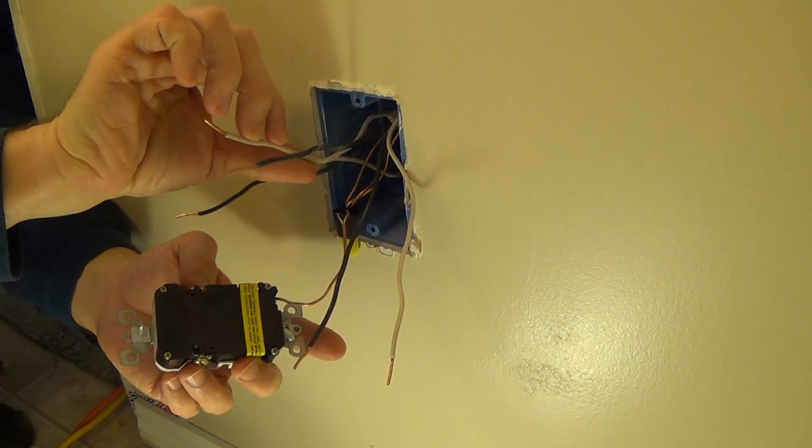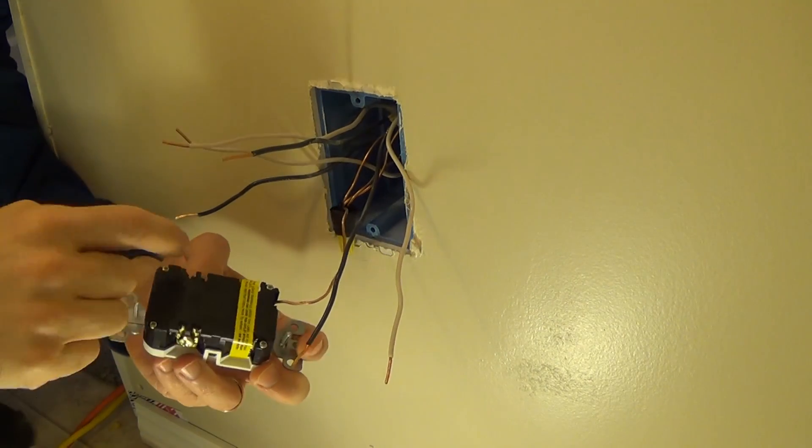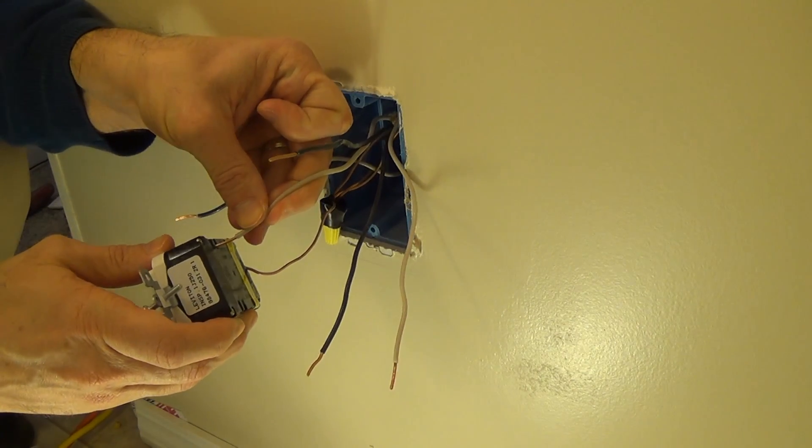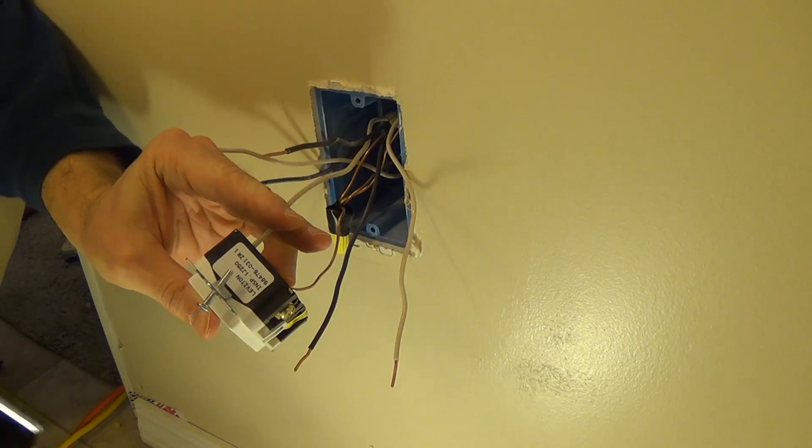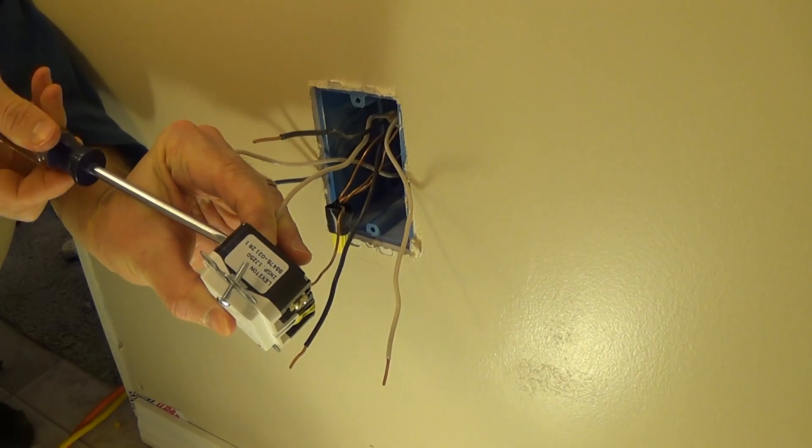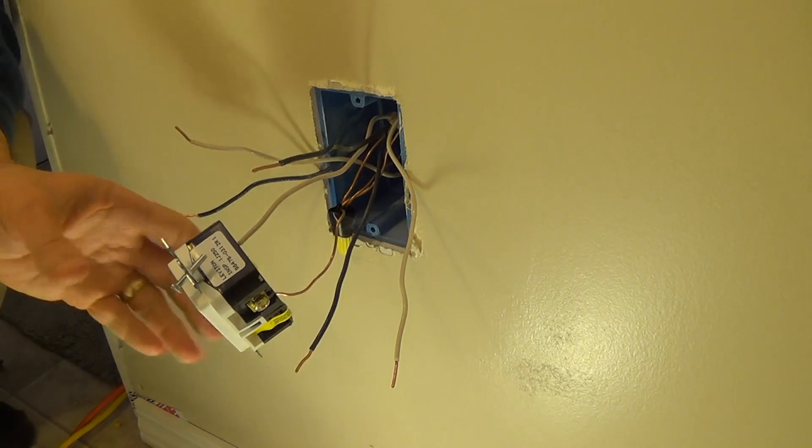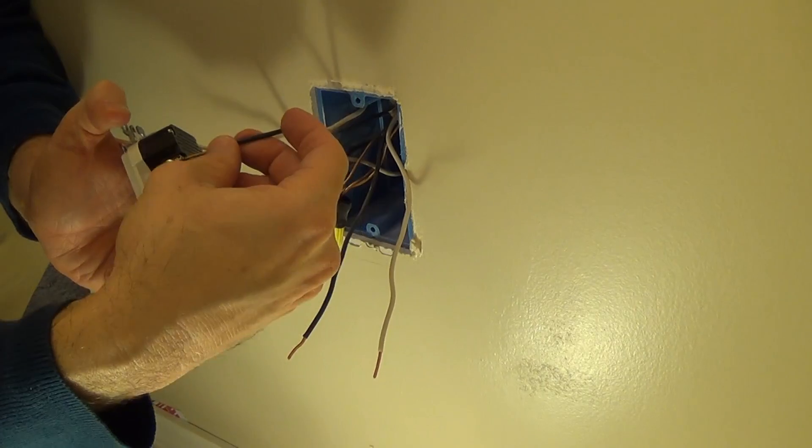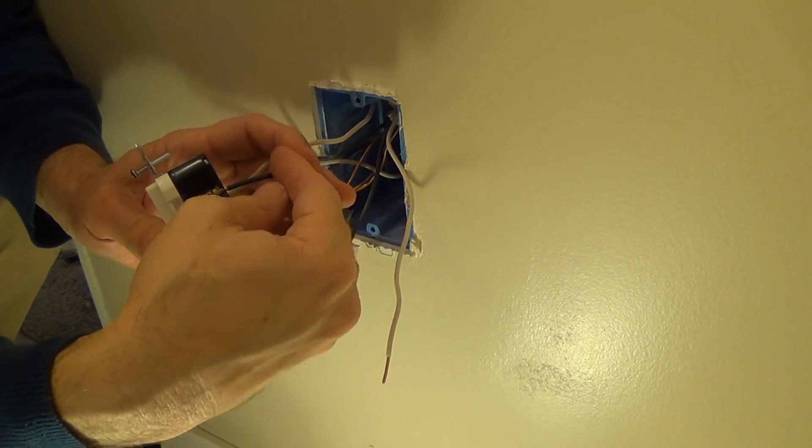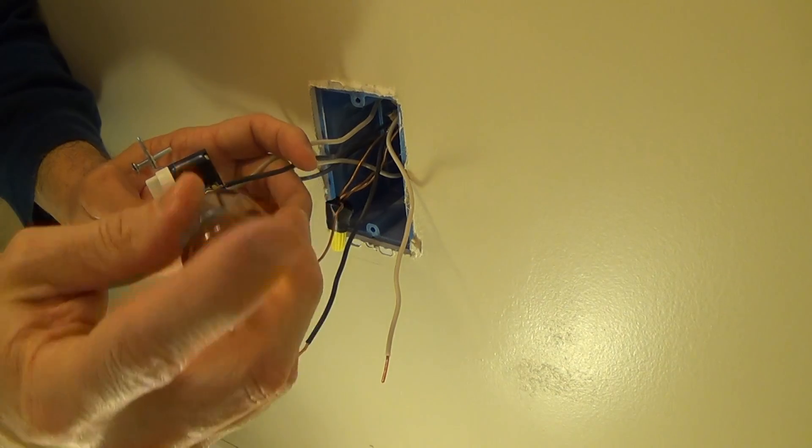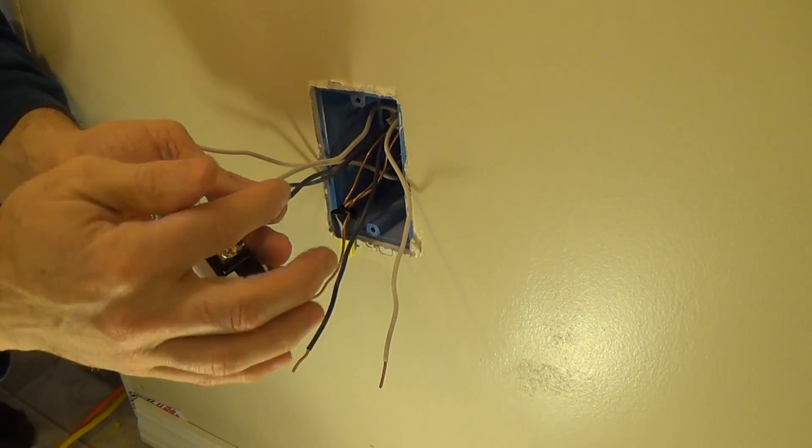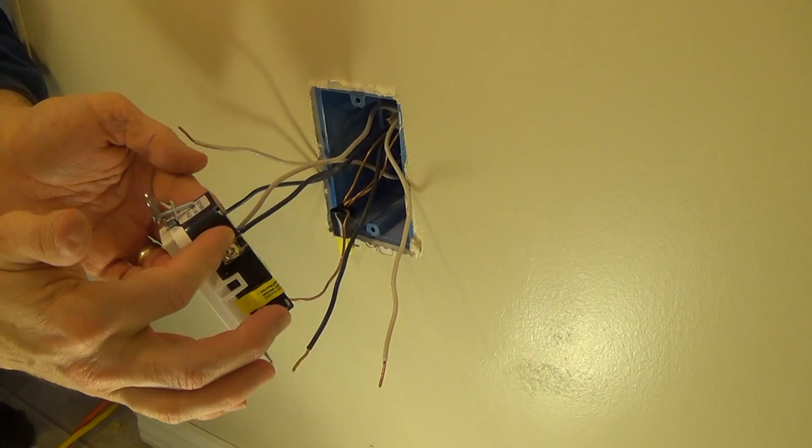So we're gonna go ahead and stick in the line load wires now. We have gold, silver, and both of them have little plates here. So we're gonna go underneath and connect the white wire like that. And then we're gonna go underneath this plate and then secure the black wire to the gold terminal just like that. So we know that the hot wires, the line wires, are connected in their proper location.